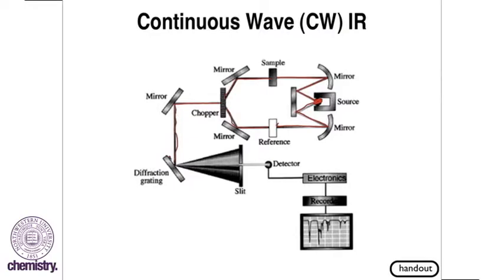All of that information goes to a detector, is amplified, printed out on a piece of chart paper, and that's how you collect IR spectra on a CW-IR.